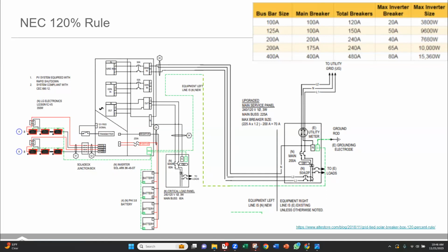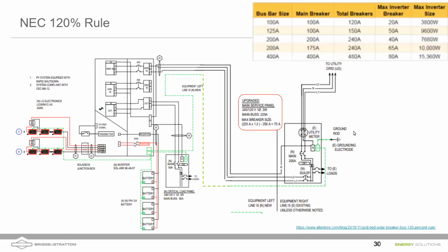and we're feeding 50 amps onto a backfed breaker on our main electrical panel. When we went out to this house, in the top right corner we have a little chart. It says if we have a 200 amp panel with a 200 amp bus, the maximum we could theoretically backfeed is 40 amps. Well, the Sol-Ark 8K has a 50 amp backfed breaker. So we could do one of 2 things. One, we could derate the main to a 175 amp main breaker, or in our case, what we did, go ahead and click. Sorry, go back.